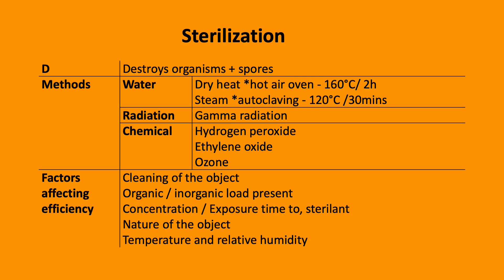Sterilisation also removes spores and can be done in one of three ways: by dry heat in a hot oven at 160 degrees over 2 hours; steam via autoclaving at 120 degrees C over 30 minutes; or radiation with gamma radiation, or chemical agents including hydrogen peroxide, ethylene oxide and ozone. Factors affecting sterilisation efficiency include the cleaning of the object, the organic load, the concentration and exposure time of the sterilant, the nature of the object, and the temperature and relative humidity.